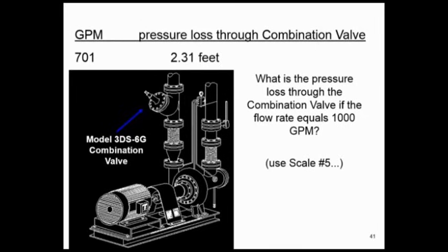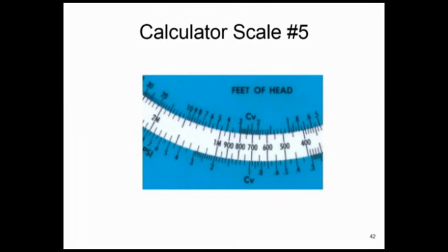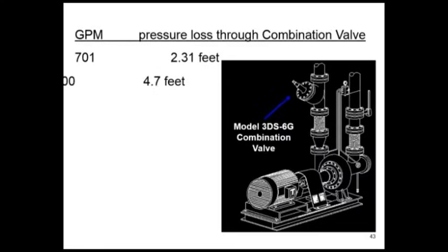Now, if we have the system sizer, we go to scale 5, and we just plug in what we know. See the GPM at 701. By the way, 2.31 feet is a pound, and so you see pound on the bottom of the system sizer where it says CV1, that's pounds. At the top is 2.31 feet at 701 GPM, so now we know the setting. We know that at 701 GPM, the pressure drop is 1 pound, 2.31 feet. They don't change anything. Go with the 1M, which is 1,000, and you see your pressure drop now is over 2 pounds or 4.6 feet roughly. If you have the Android or the Apple-based version, it'll give you the number reading out directly, if you like it that way. So here we go.